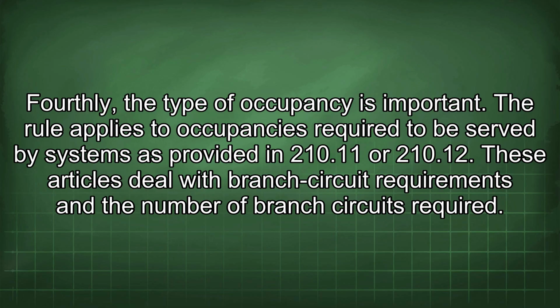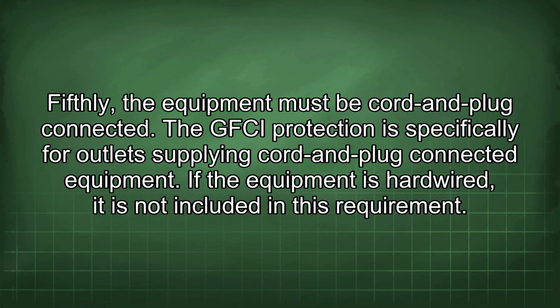Fourthly, the type of occupancy is important. The rule applies to occupancies required to be served by systems as provided in 210.11 or 210.12. These articles deal with branch circuit requirements and the number of branch circuits required. Fifthly, the equipment must be cord and plug connected. The GFCI protection is specifically for outlets supplying cord and plug connected equipment. If the equipment is hardwired, it is not included in this requirement.